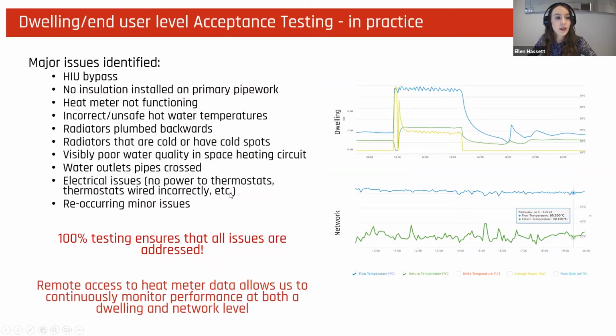Next slide. So in practice, a collaborative, structured process has been proven to achieve excellent performance. Major issues can be identified before handover, such as HIU bypasses, radiators plumbed backwards or upside down, electrical issues, and testing 100% of dwellings ensures that all of these issues are addressed.